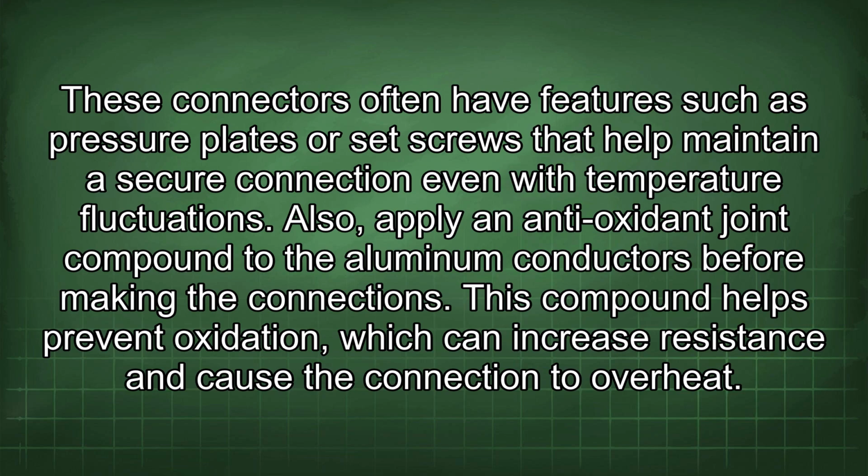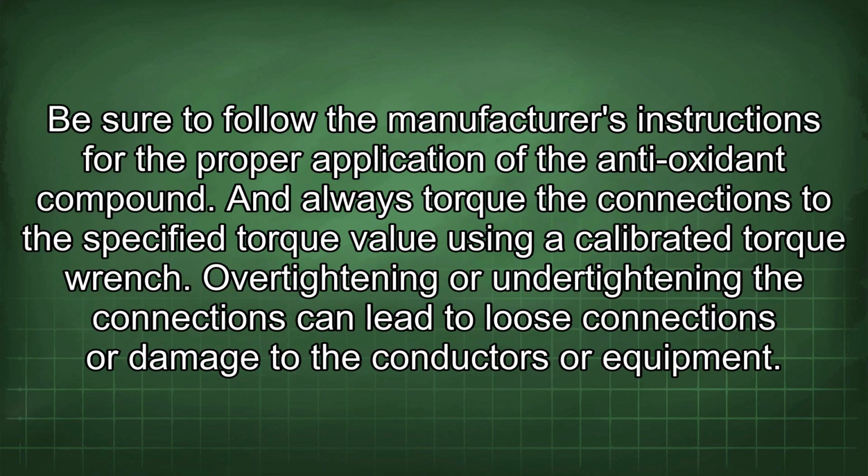This compound helps prevent oxidation, which can increase resistance and cause the connection to overheat. Be sure to follow the manufacturer's instructions for the proper application of the antioxidant compound. And always torque the connections to the specified torque value using a calibrated torque wrench. Over-tightening or under-tightening the connections can lead to loose connections or damage to the conductors or equipment.